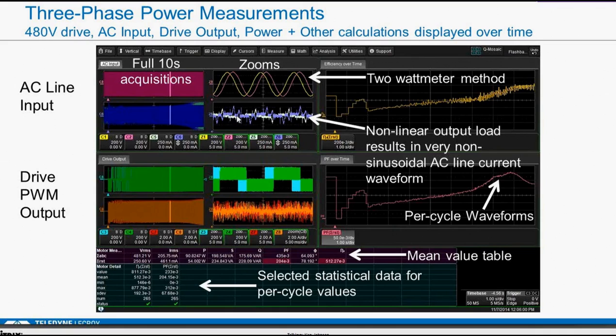So basically what you see is, in this case, a couple pulses by the nature of the inverter design. You see a couple pulses for every voltage peak. That's how it's drawing the current, relating to how the power electronics are working inside the drive. So even if you think you have a nice AC line current, nice and sinusoidal, you don't, right? This is the reality of the world today. There's power electronics everywhere, and they draw in a very nonlinear way.